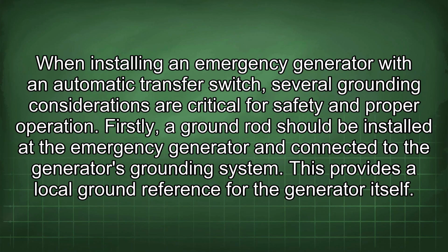When installing an emergency generator with an automatic transfer switch, several grounding considerations are critical for safety and proper operation. Firstly, a ground rod should be installed at the emergency generator and connected to the generator's grounding system. This provides a local ground reference for the generator itself.